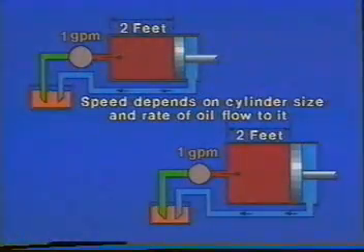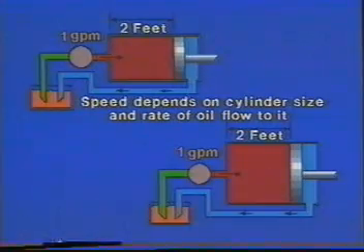I suppose you already know that increasing the relief setting doesn't increase the speed of a cylinder or motor. It's the amount of oil available and the size of the actuator that determines speed. That's why little cylinders move faster than big ones in the same system. Increasing the pressure will let you clamp tighter or move a heavier load. But be sure you don't try to exceed what the system is designed to do.